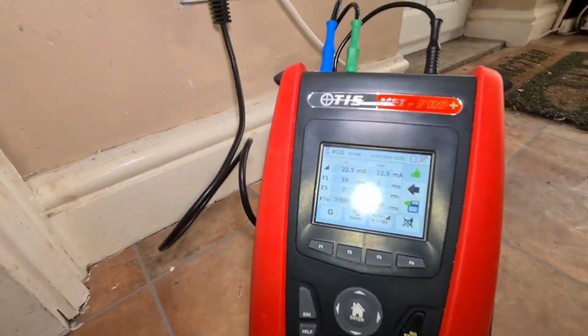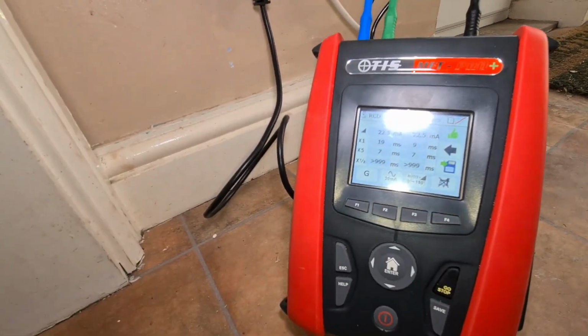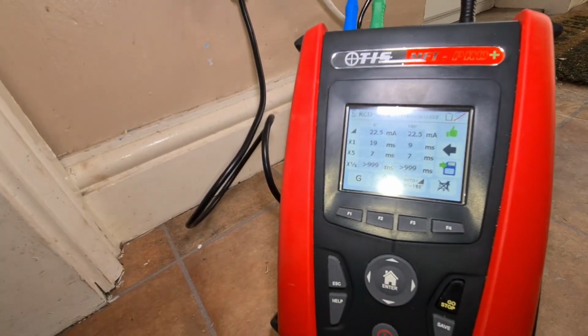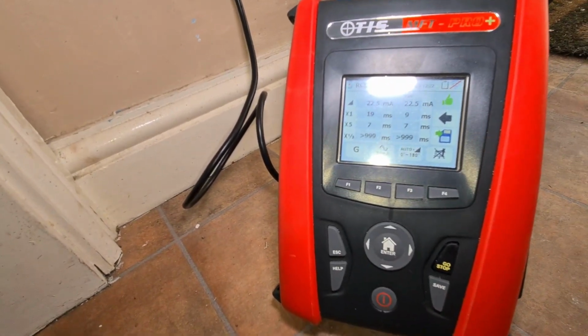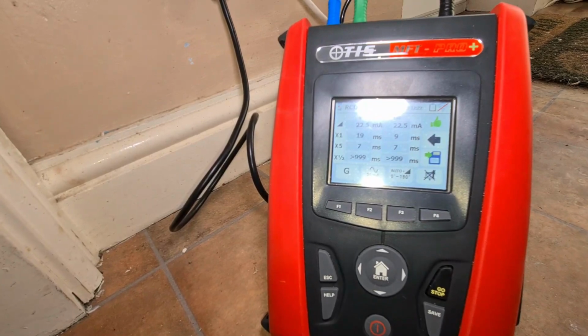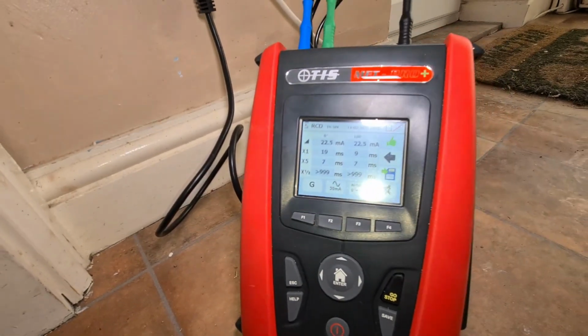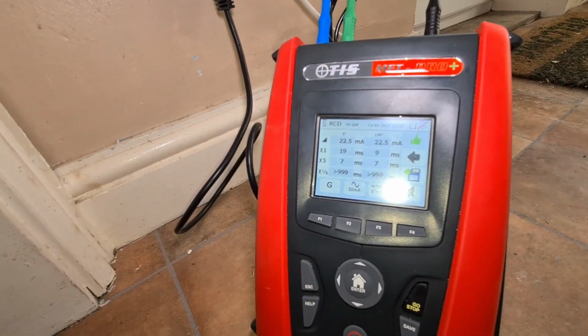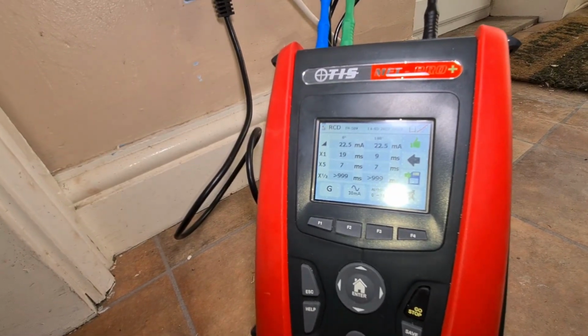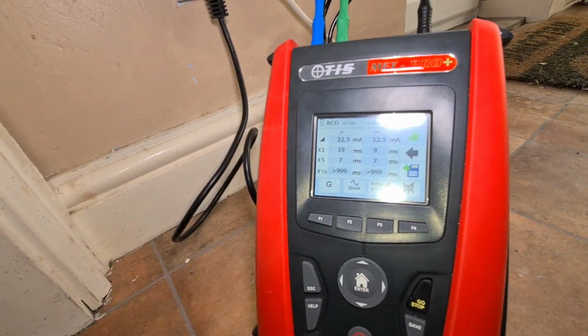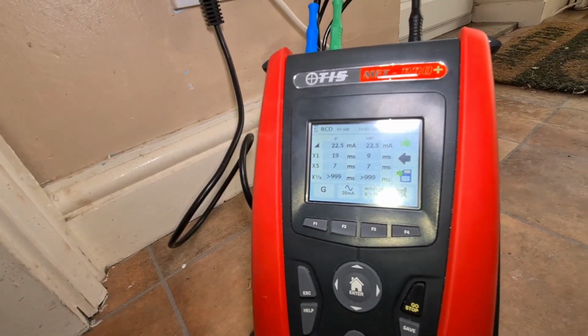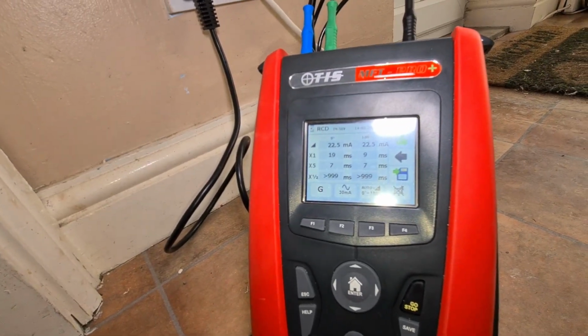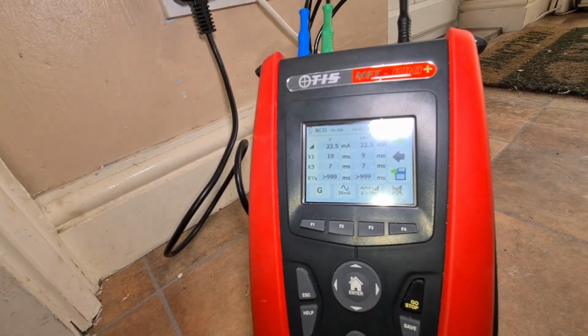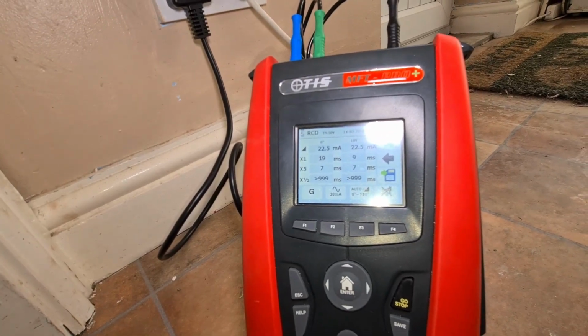So there we go, we have got our 0 and 180 degree tests on the RCD, and you can see we tripped out on the ramp at 22.5 milliamps, which is okay, that's nothing wrong with that. Times 1 at 19 and 9, and times 5 at 7 milliseconds, and it didn't trip at all on the half-time test. So that's a healthy RCD on that circuit.